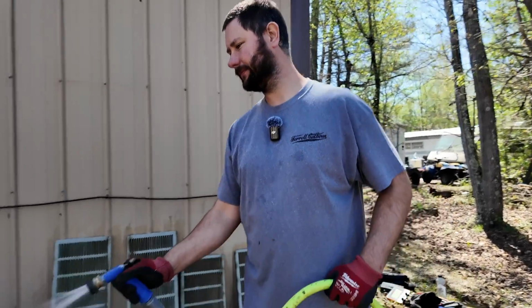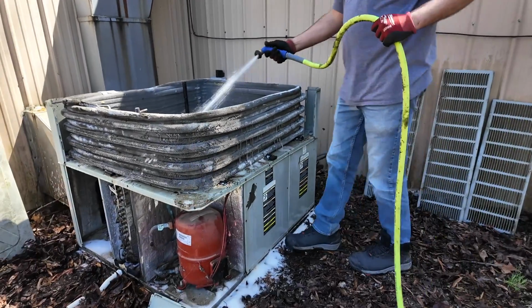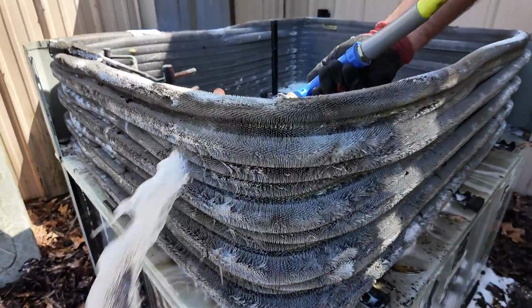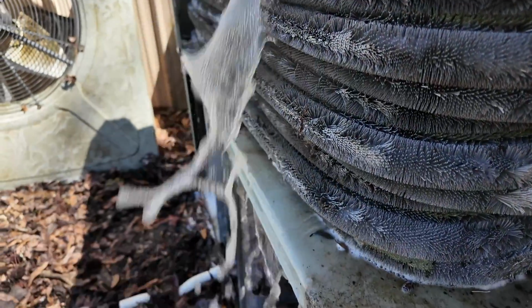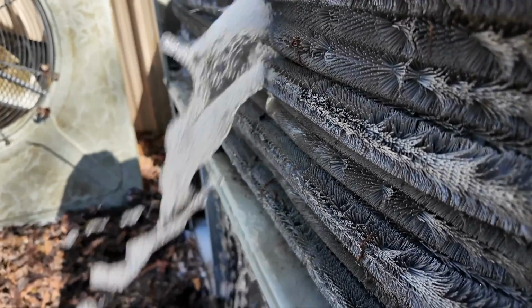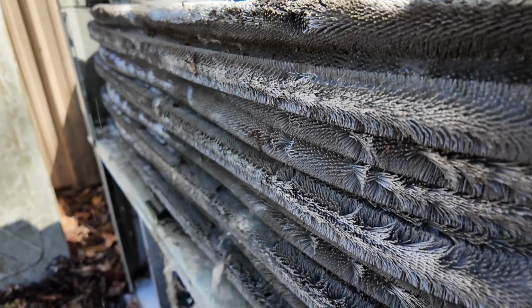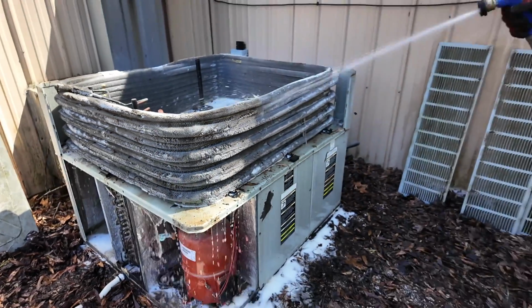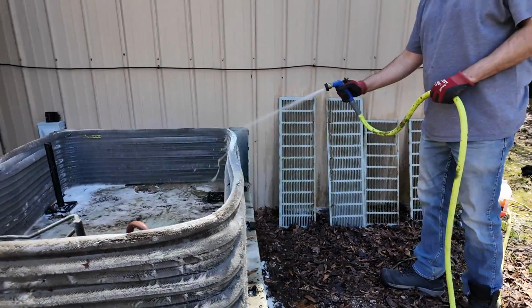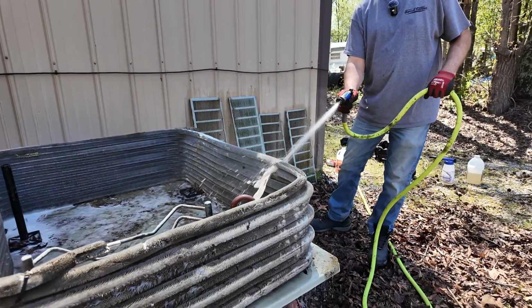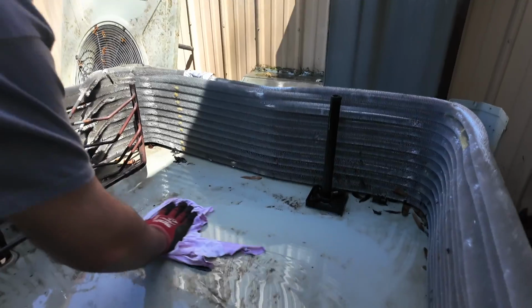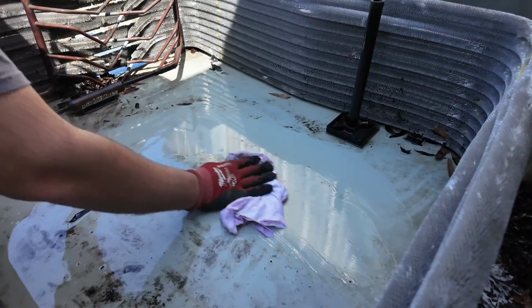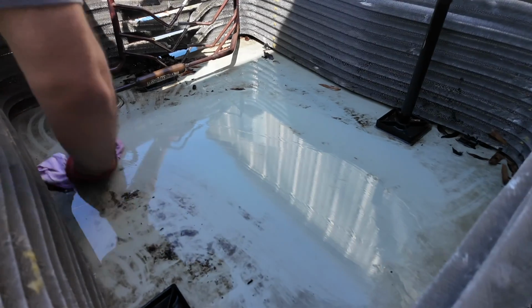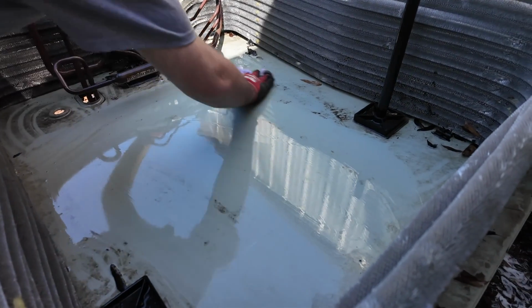Now we're ready to wash off that coil cleaner. We're gonna clean it from the outside in, the inside out, and make sure we do a good job. You can see the dirt though. Take a look. See that brown water? How do we know when it's clean? When there's no more brown water. Take that rag, get in here, wipe it off. Look at that. Look at that. That is beautiful. Absolutely beautiful.